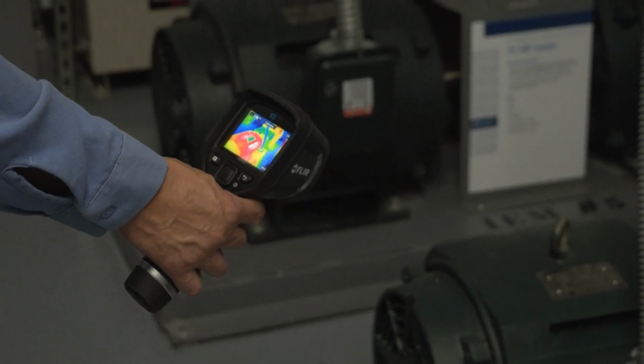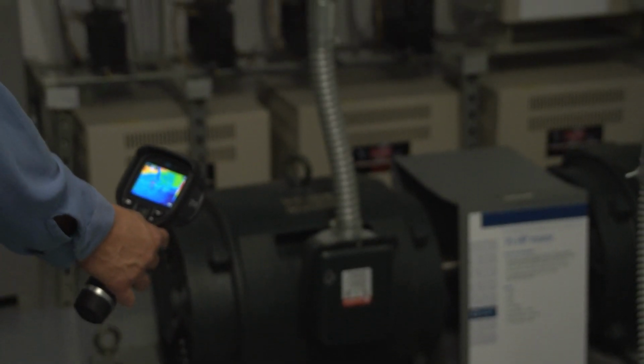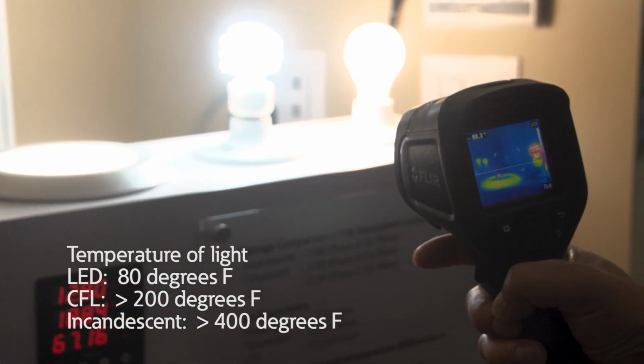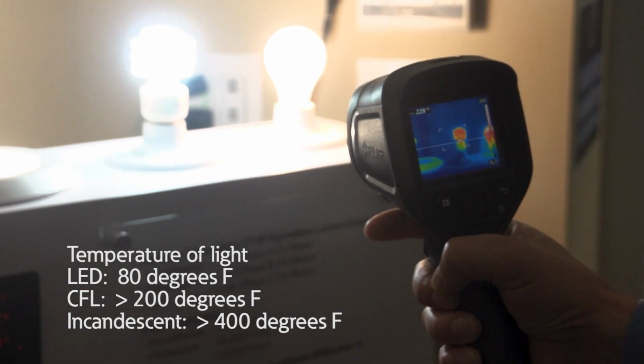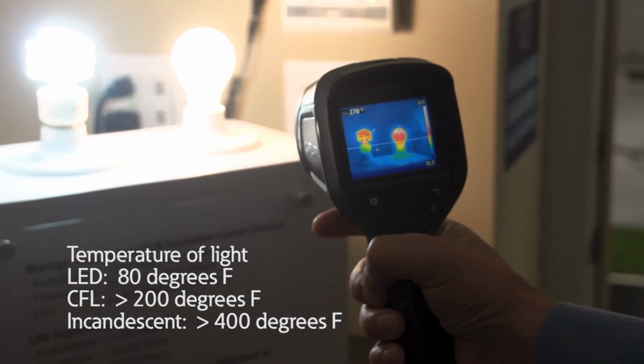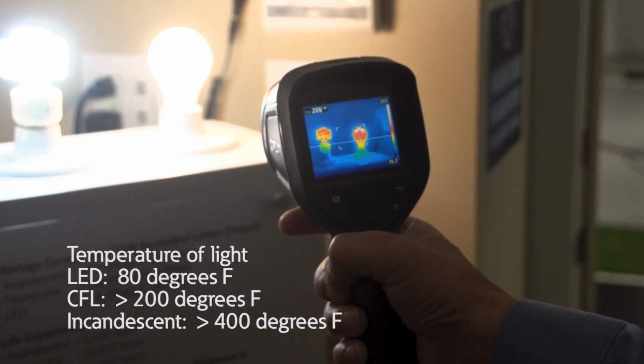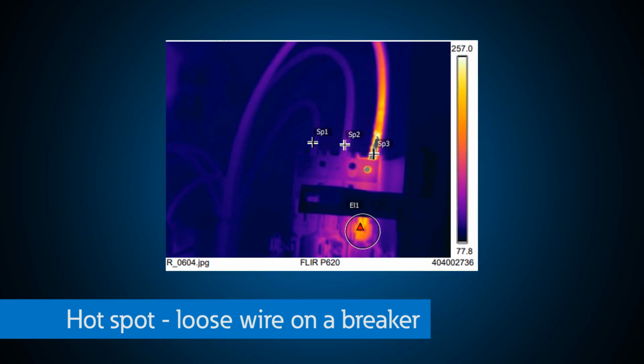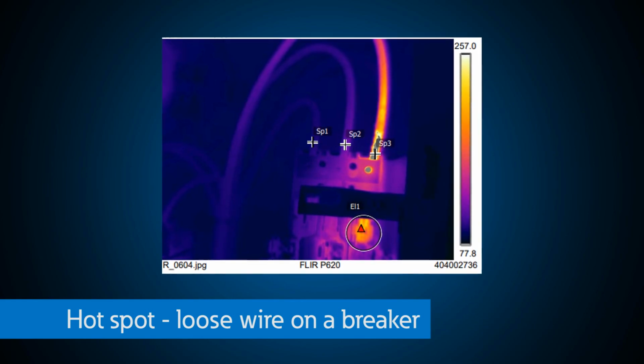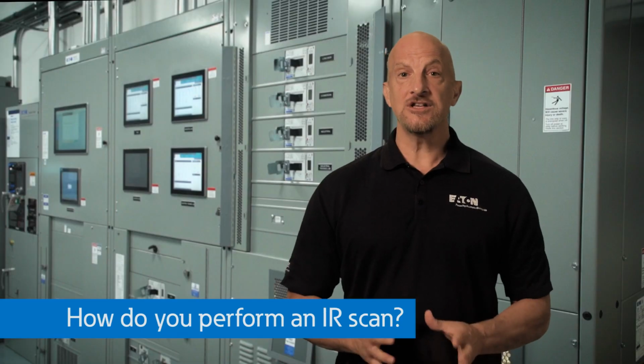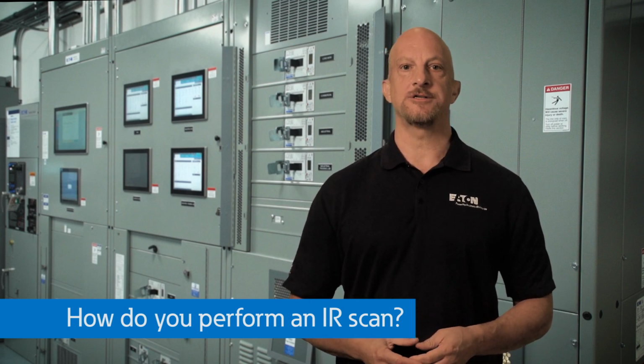IR scanning is done to identify temperatures above a baseline as indication of an impending failure. Looking at three different types of lights, including LED, fluorescent, and incandescent, highlights the significant difference in operating temperature using an IR camera. Likewise, thermal issues in switchgear, conductors, breakers, and other electrical connections become equally apparent to a trained thermographer. The next question is, how do you perform an IR scan?